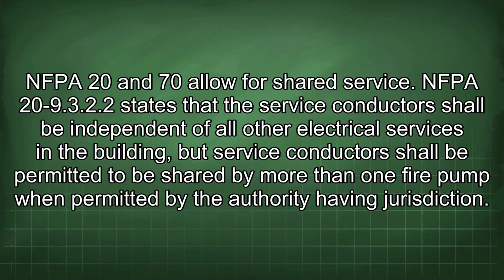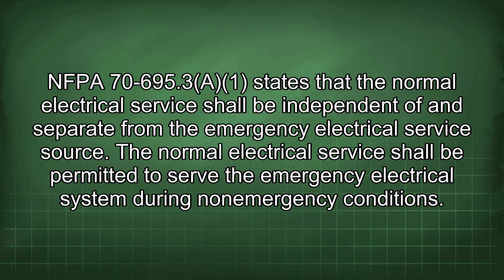NFPA 20 and 70 allow for shared service. NFPA 20-9.3.2.2 states that the service conductor shall be independent of all other electrical services in the building, but service conductors shall be permitted to be shared by more than one fire pump when permitted by the authority having jurisdiction.